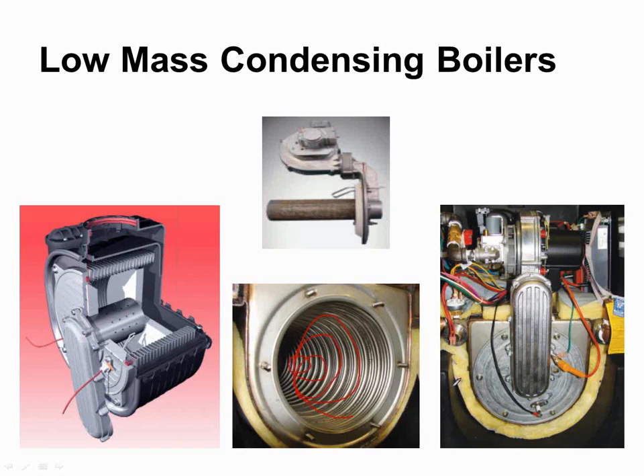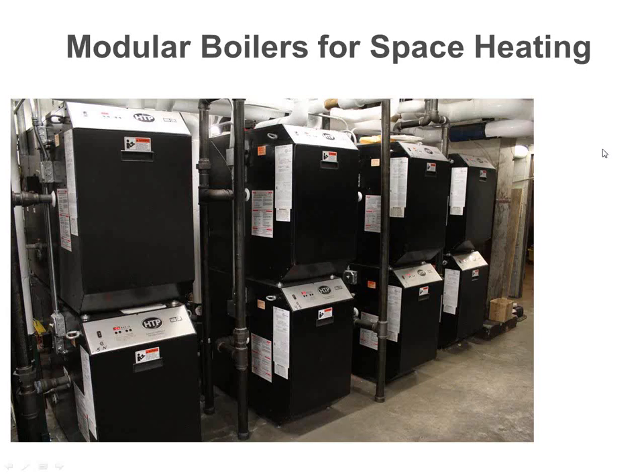What Ryan's circling right now are the actual tubes, looking at them from the fire side, if you want to call it that. And above you is actually the burner itself with the gas valve and the blower motor. The picture furthest to the right is actually just showing what the whole front of the boiler looks like after you take the cover off. So it's a lot different than the old cast iron with atmospheric burners.